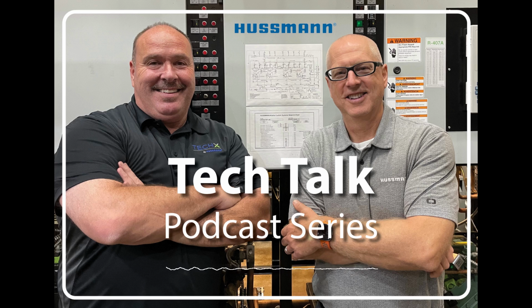Sure, Paul. Let's start with condensers that use V-belt drives for fans. They will need a V-belt inspection and possible replacement. It is important to use the manufacturer's recommended V-belt size. When replacing worn or broken V-belts, it's important to inspect belt tension and alignment. I would recommend checking out Browning's V-belt training on their YouTube page. There you'll find more details on V-belt tension and alignment. It's also important to inspect the pulleys for wear and grooves.